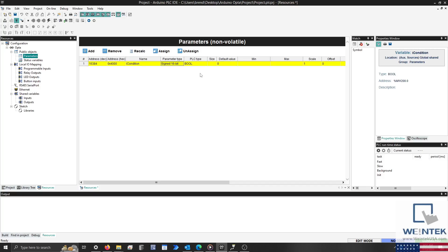From what I've found, the PLC Type determines how the variable will be interpreted within the project, whereas the Parameter Type determines the data length and type as referenced by the client. As an example, the Parameter Type may be configured as an integer allowing numeric entry, but if the PLC Type is bool, any number over 0 is considered true.